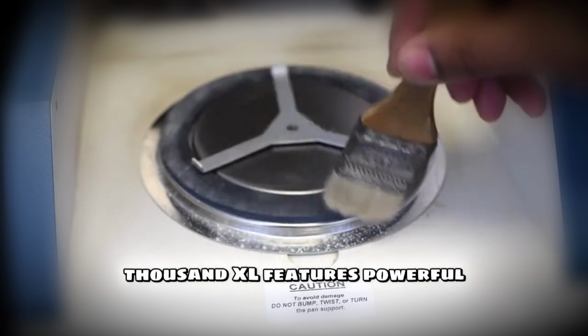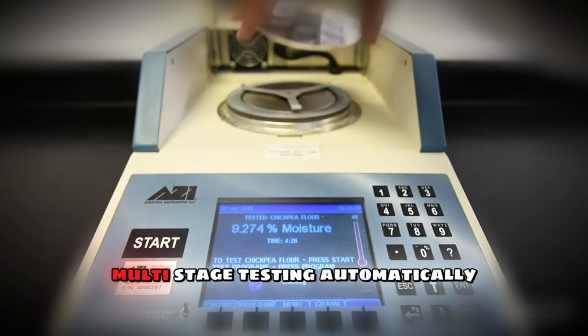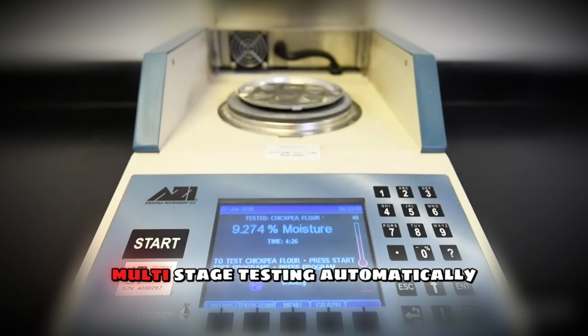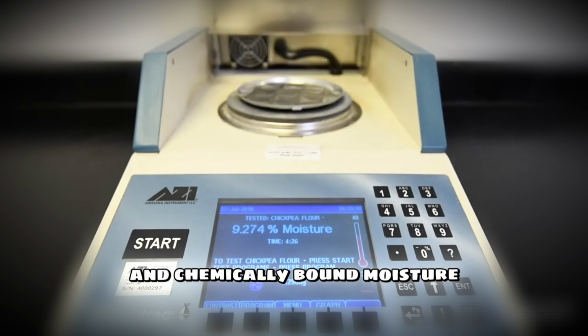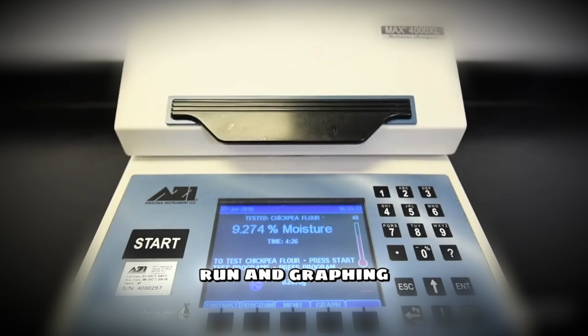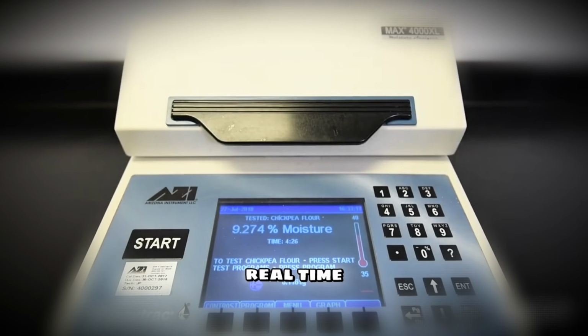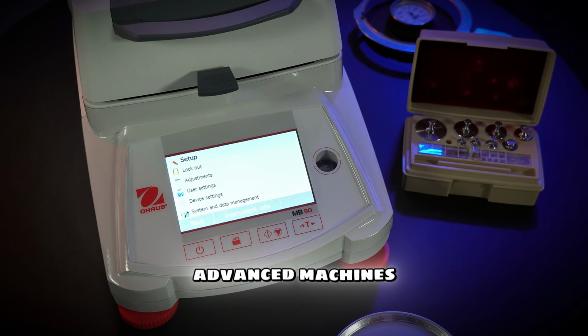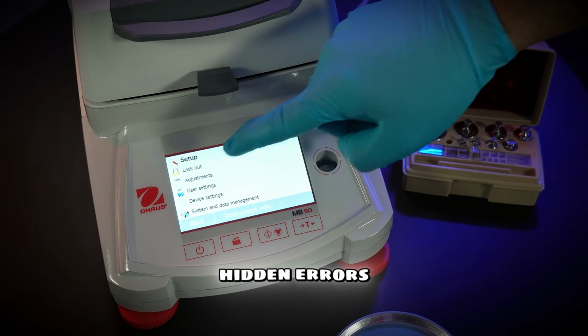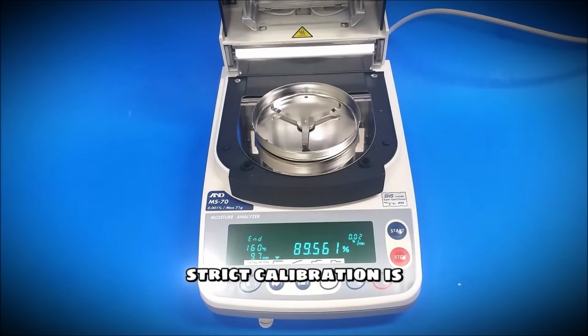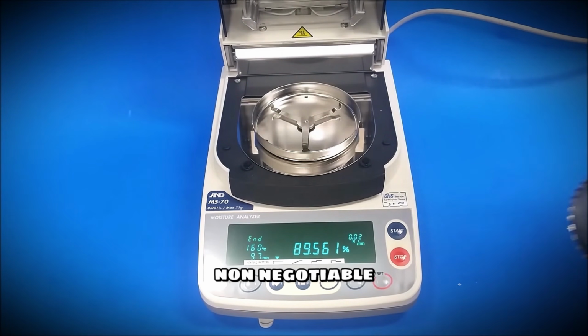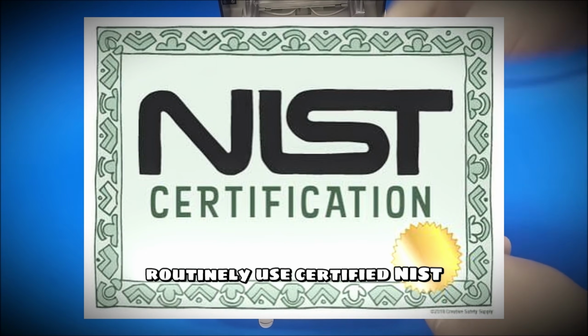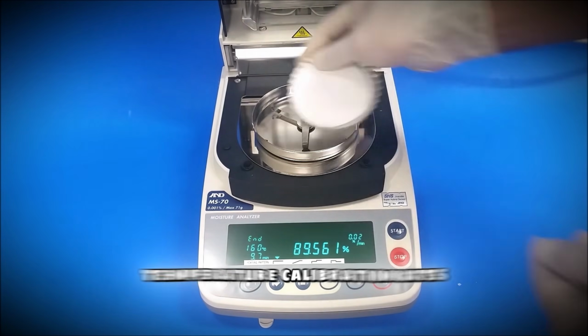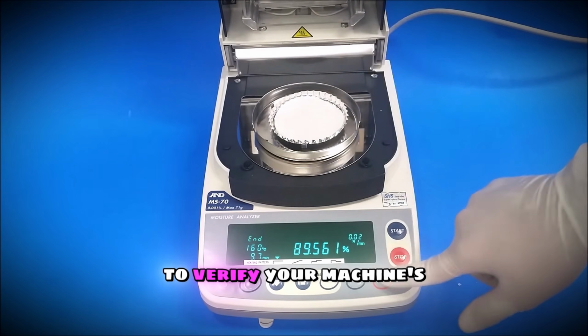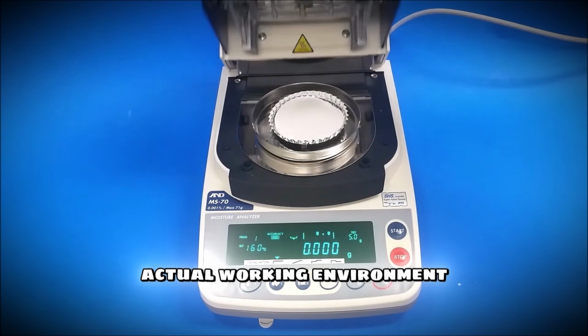The Max 4000 XL features powerful multi-stage testing, automatically measuring both surface and chemically bound moisture in a single run and graphing it all in real time. To ensure these advanced machines do not fall victim to the hidden errors we discussed earlier, strict calibration is non-negotiable. Routinely use certified NIST traceable weights and temperature calibration kits to verify your machine's accuracy in its actual working environment.